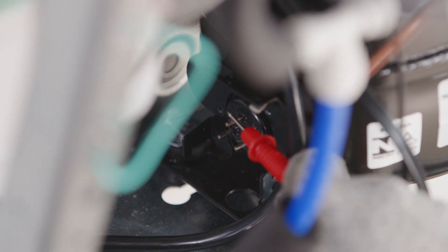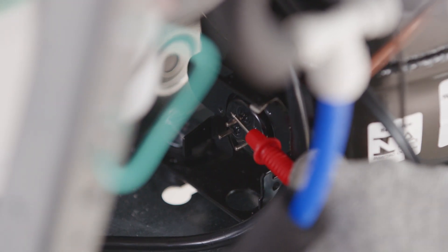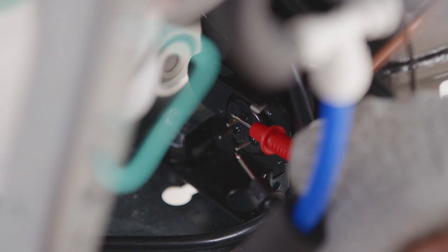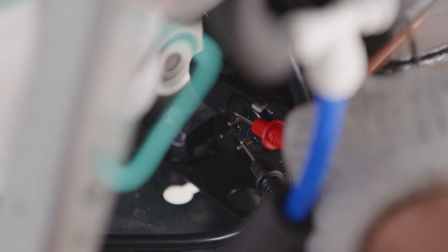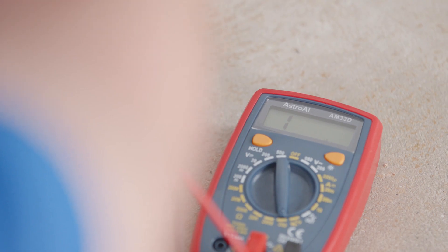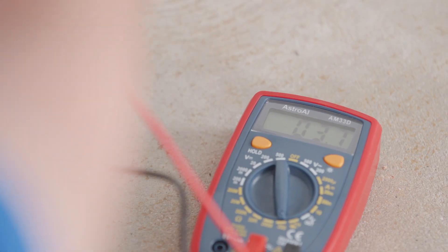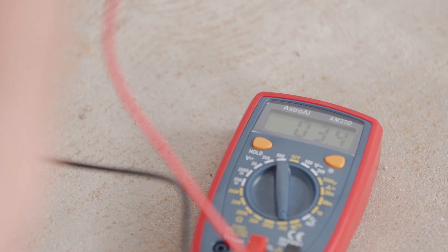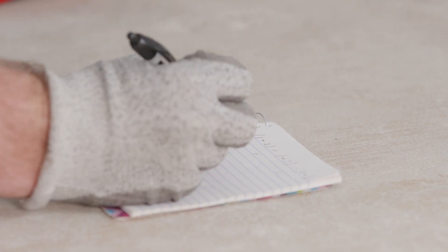Place the red electrical probe to the top coil, the common coil. Place the black electrical probe to the run coil at the bottom right. Check the reading on the multimeter and write down the results.